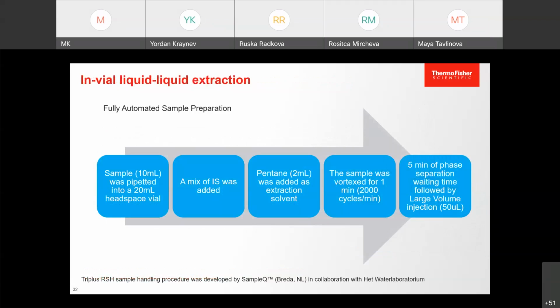It's in-vial liquid extraction. You can see how we are fully automatic preparing this on the TriPlus autosampler. We are adding internal standards, then vortexing, that means mixing at 2000 cycles per minute, and then we are taking only part of it and injecting into the GC-MS triple quadrupole.